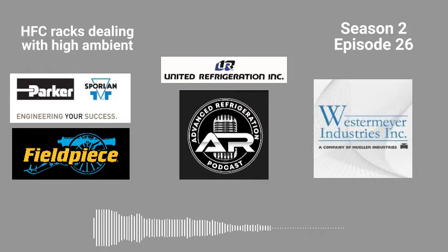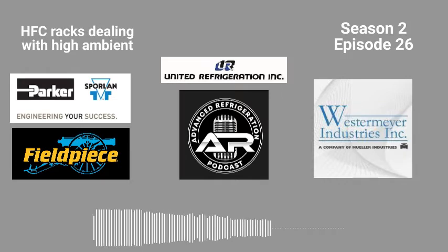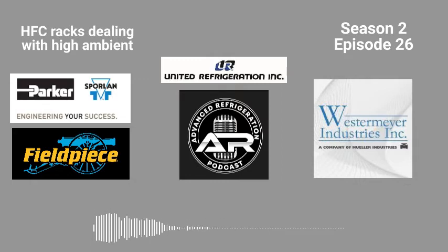So make sure one of the checks that you should be doing is valving off the receiver repressurization valve, the line going from the discharge line over to the receiver. Once you shut it off, your subcooling will go away, your head pressure will come down, your TD will be straight up, but then all of a sudden you'll watch the dial on the receiver go from 35, 45, 55, 65, 95, oh shit, and then you end up turning the valve back on so you don't pop anything off.